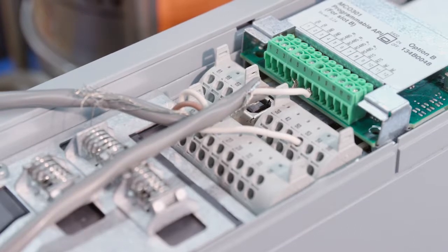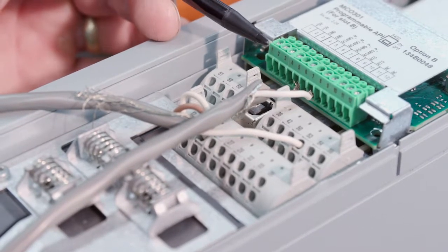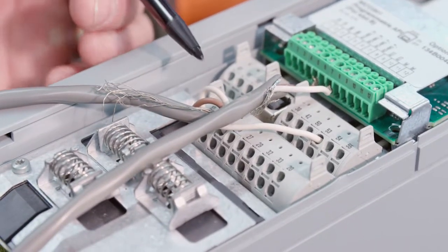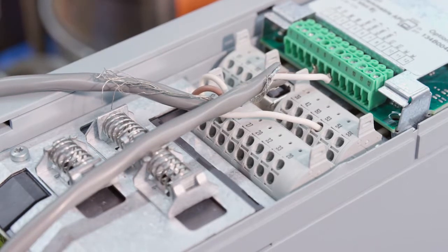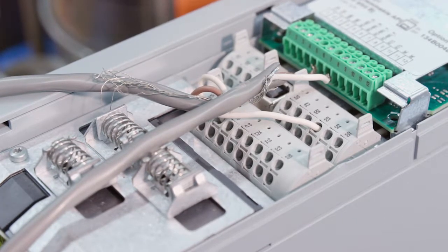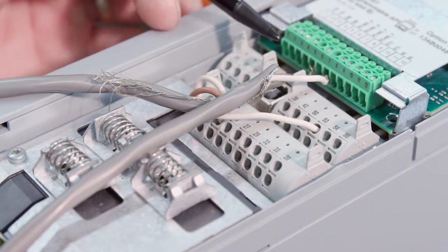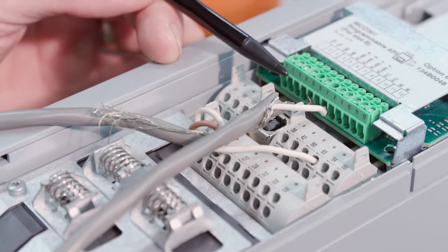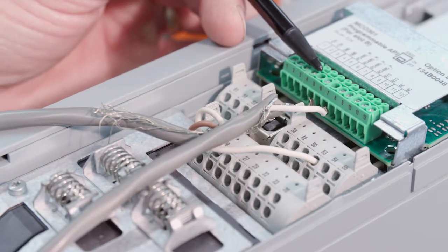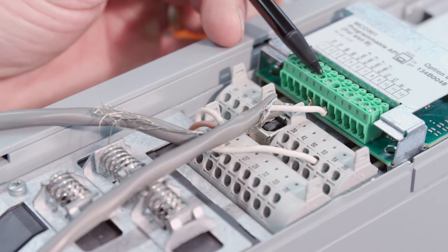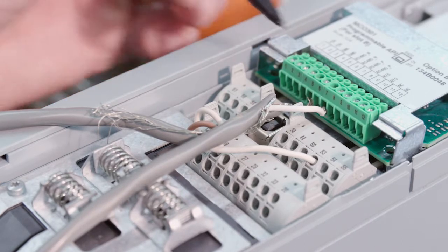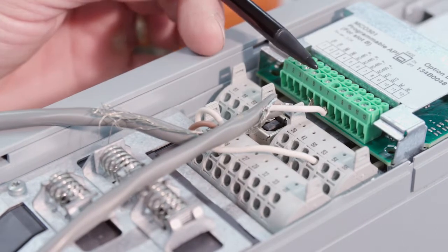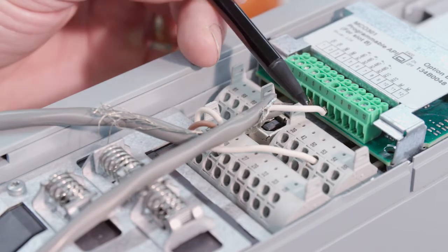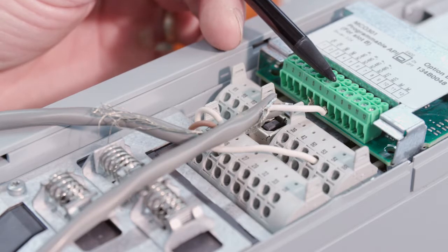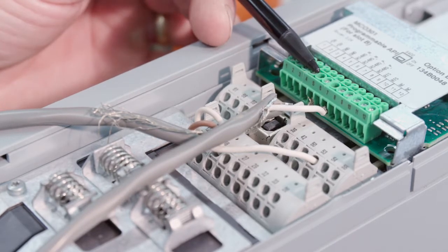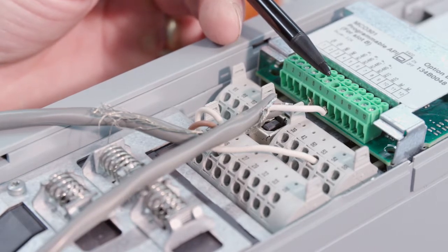And so we're going to look at the communication cable between our 2 drives, our transducer hookup. We still need a start jumper, and then we're also going to take you through the input and the output, which doesn't change. So let's first start with the communication cable. Again, this is connected to our other drive here, and we are connecting between 5 on the MCO 301 on our drive here to the same 5 terminal on pump number 1. And we're using the white to connect to 7, and we just want to make sure that you have 5 to 5 and 7 to 7 on the other drive.